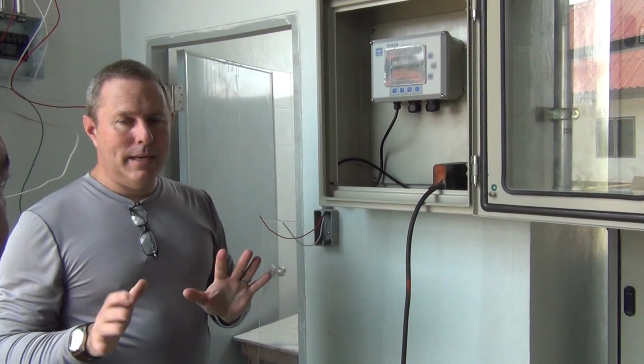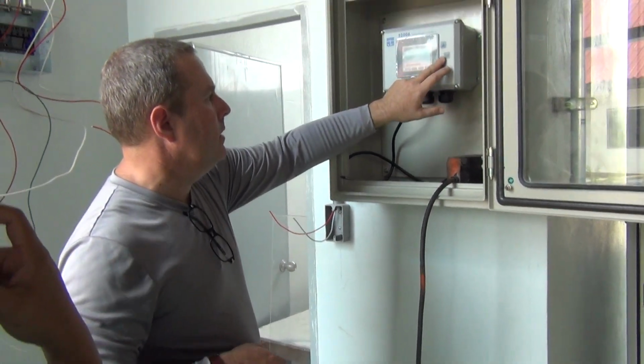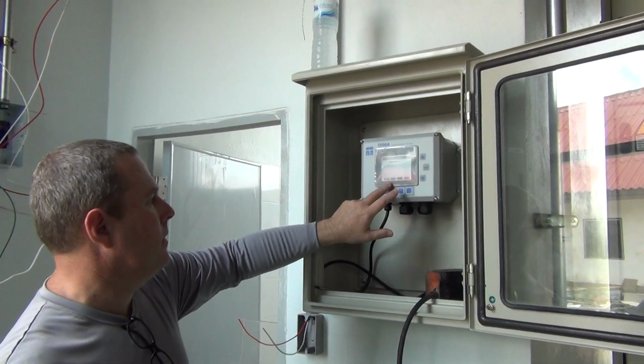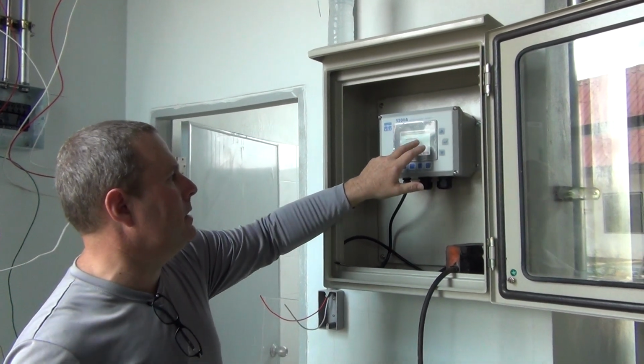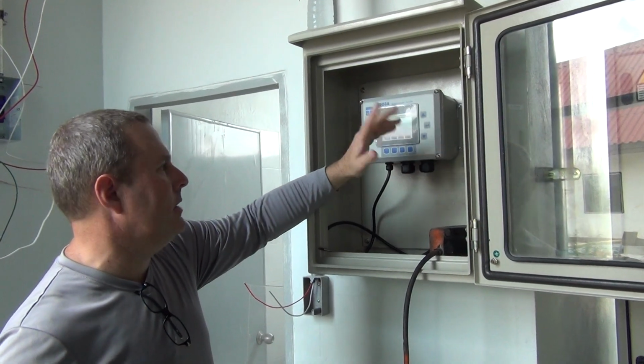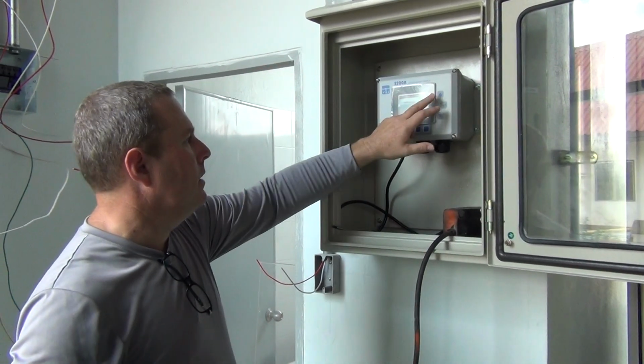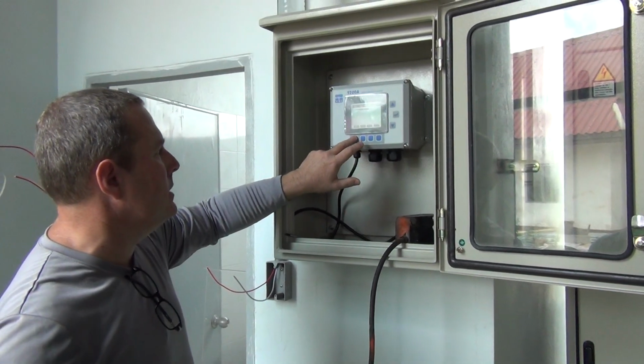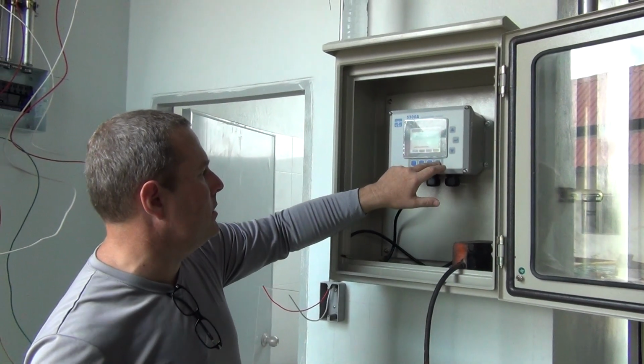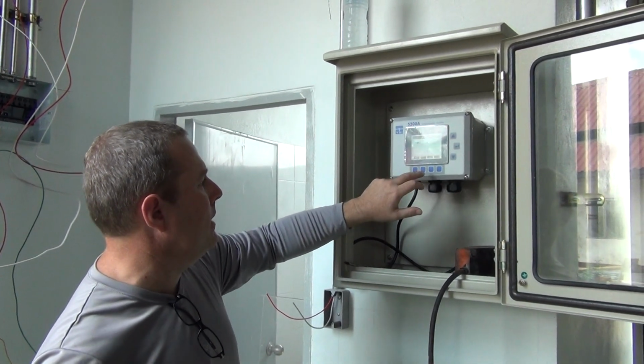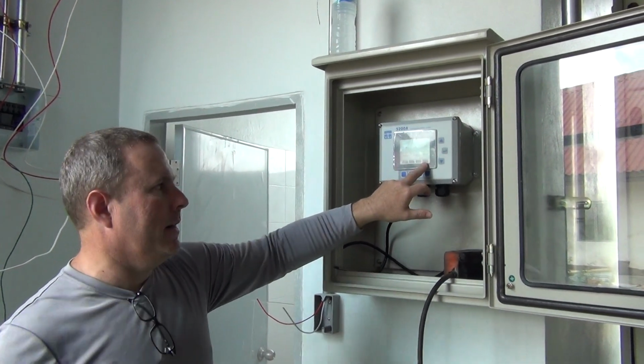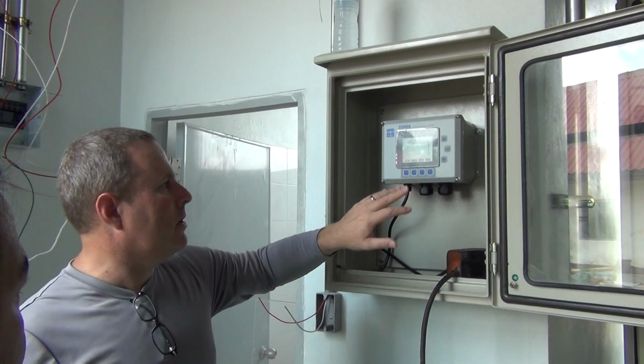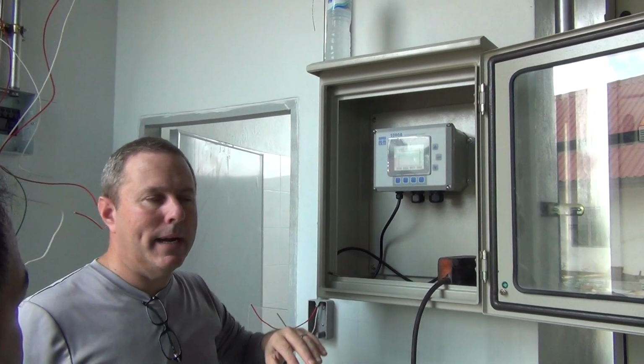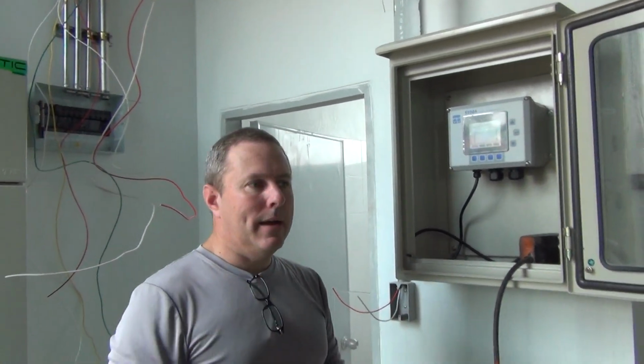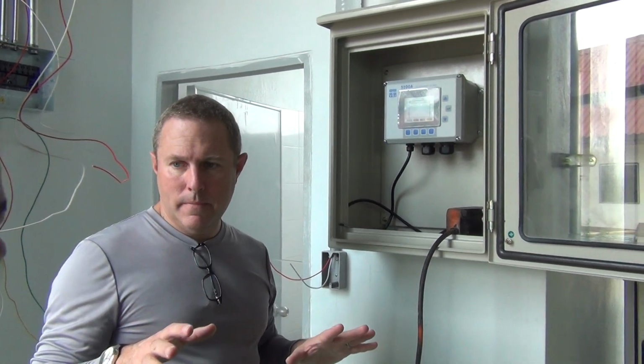Okay. If you did later on, all you would do is go in, enable it, and then set how long you wanted it to be active at a time. Like this is set for 5 minutes, you can make it 10 hours, 1 minute, whatever you want. And what would happen is that when you go to the menu, I'll show you here in just a second, on your first menu button, you see service hold right here. So before you would do anything, you would press service hold. It's going to say it's not enabled because we don't have it enabled right now. But if it was enabled, it would start counting down and then you could do work and it would not data log anything during that time. Is this clear? Okay, yes.